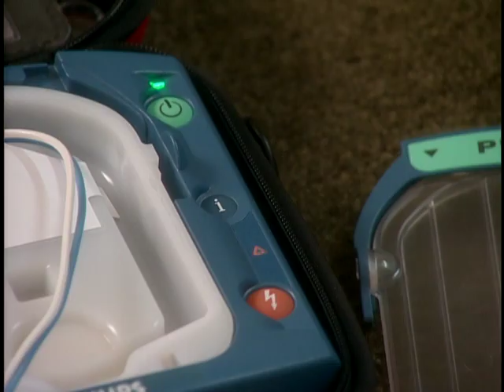Analyzing. The caution light flashes as a reminder that no one should touch or move the patient, which may interfere with the analysis. If a shock is needed, the orange shock button will start flashing and the voice will tell you, "Shock advised. Stay clear of patient. Press the flashing orange button now." Make sure no one is touching the patient. Then press the flashing orange shock button.